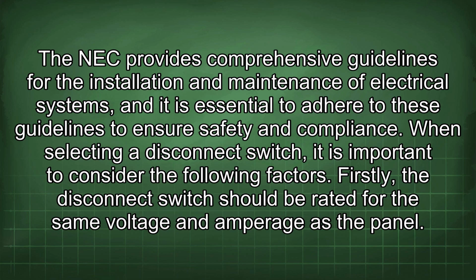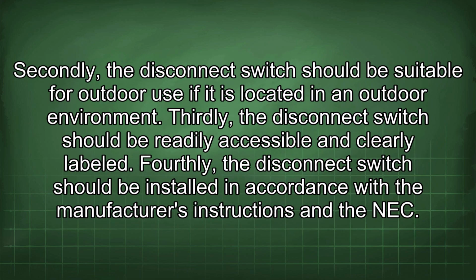When selecting a disconnect switch, it is important to consider the following factors. Firstly, the disconnect switch should be rated for the same voltage and amperage as the panel. Secondly, the disconnect switch should be suitable for outdoor use if it is located in an outdoor environment. Thirdly, the disconnect switch should be readily accessible and clearly labeled. Fourthly, the disconnect switch should be installed in accordance with the manufacturer's instructions and the NEC.